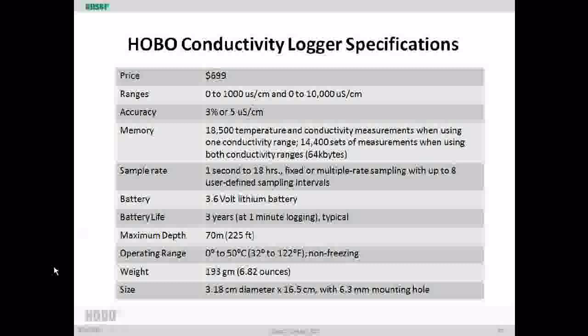There's toroidal sensors which use coils to detect the changes in capacitance due to the conductivity changes. Ours actually uses a couple of probes within the sensor, so it's not a toroidal approach. It's a fairly unique approach, but basically it's a capacitive approach for measuring the changes in conductivity.